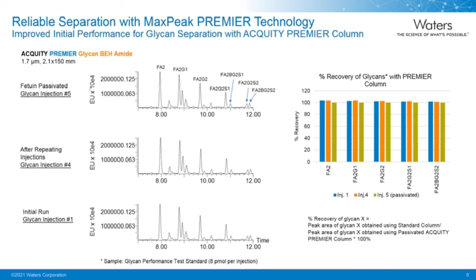Those glycan profiles acquired using the Premier version of the amide column were seen to be comparable both before and after conditioning-based Fetuin passivation. As demonstrated here, between injections 1, 4, and 5, the recovery of individual glycans and the effective peak capacity of the separation remain consistent through those 5 injections. It is also worth mentioning that the glycan profile achieved using the Premier column was comparable to that achieved by using a fully passivated conventional column.